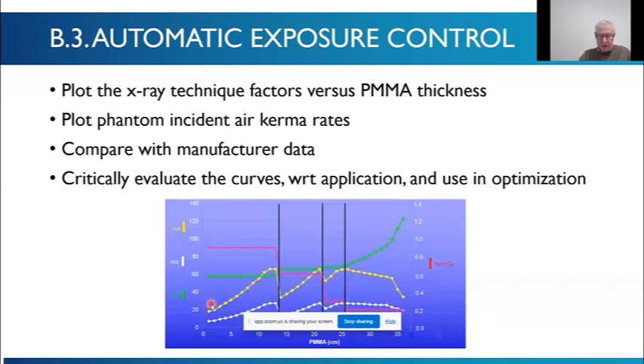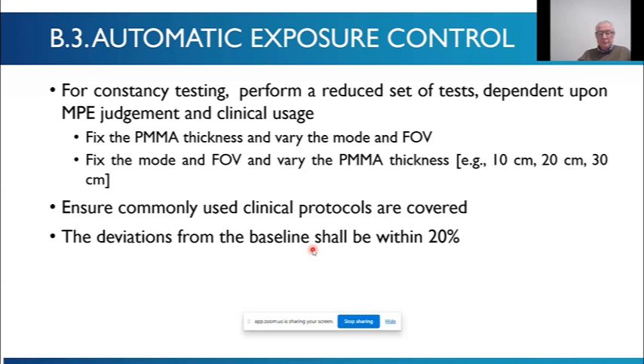And then you can see that the mA is related to the focus size bands. So here you will be on the micro focus, and then it may switch to a small focus, and then it may switch at this point to the large focus, and that's where you need the maximum amount of power to get through the patient. So this gives you an awful lot of information, and it also helps you, in effect, understand the system and helps in optimization, comparing one setting against another setting. But it takes quite a long time to gather this information, but it is very useful.